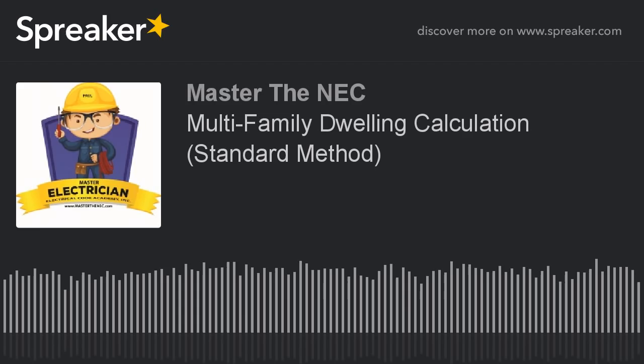So, first things first, I'm going to use 220.12, the table. That table tells me what my general lighting loads by occupancy are. And since we're dealing with dwelling units, you'll notice that in this table, it says that you use 3 VA per square foot. We said we had a 1,000 square foot unit, so obviously it's 3 VA per square foot. That's what's in Table 220.12. That's where we start first when we're going down this path. So that's step 1.